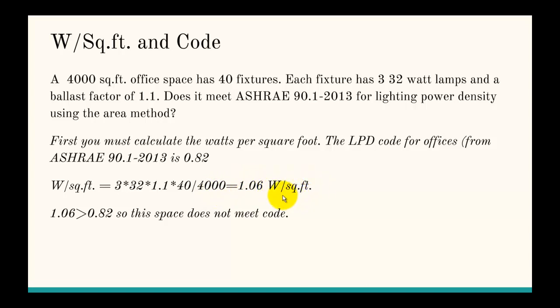Now, does it meet the code? Since the watts per square foot of 1.06 is above the 0.82 requirement, it does not meet code in this example. Thanks for watching the lighting calculation video.